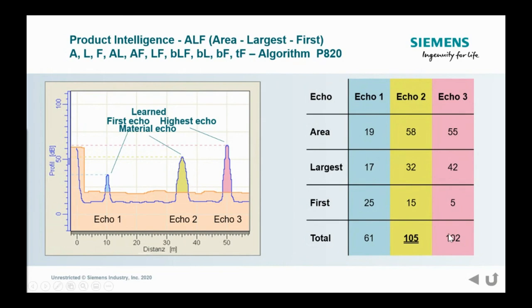This happens in the background. There isn't a way you can look at this. When you're talking echo confidence, what you will find is the echo confidence in this case is going to be zero. Actually, it's negative 58, but we don't show negative numbers, because echo confidence is the echo selected minus the score of any other echoes that you have. So you would have 105 minus 132 minus 61, basically is going to give you a zero.